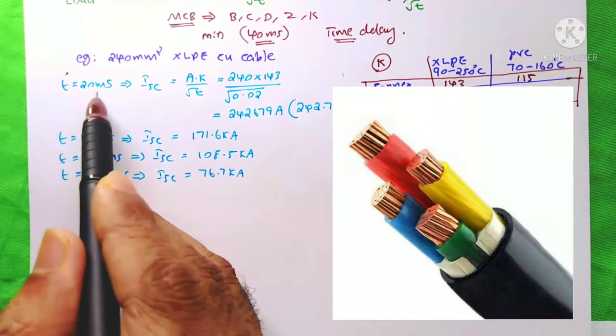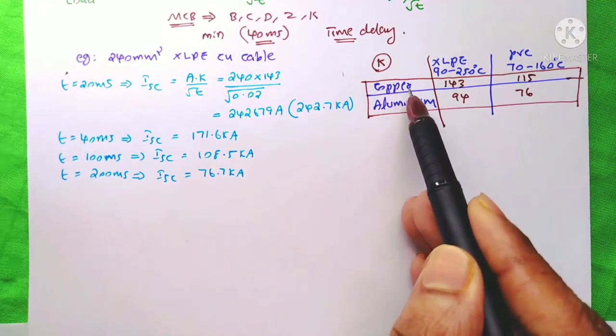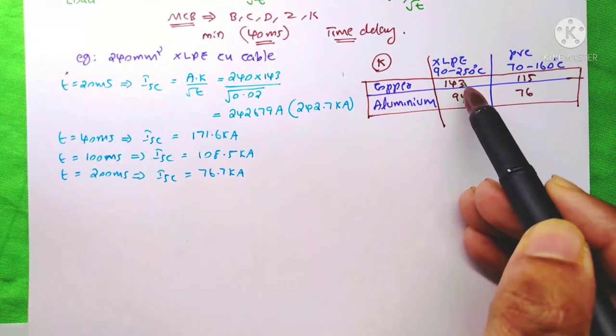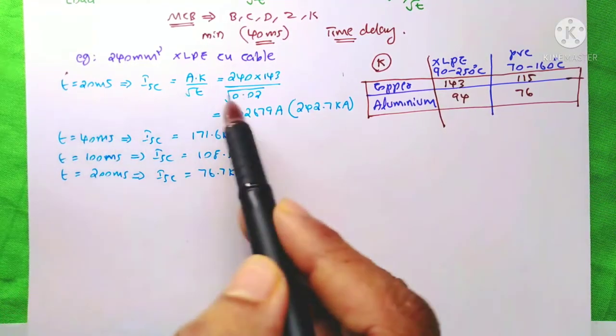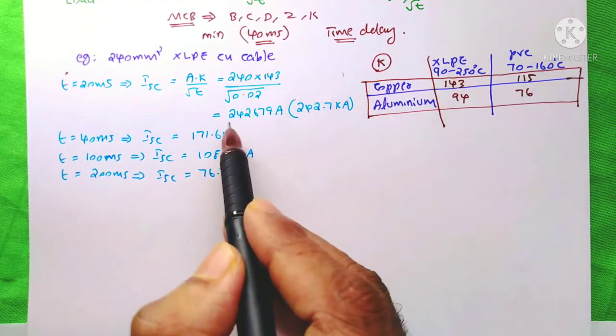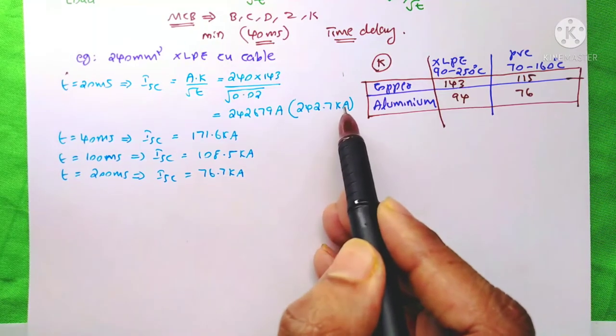When T equals 20 ms, for the constant K for copper cable, if XLPE insulated, K equals 143. 20 ms means 0.02, root of 0.02. So the answer is 242.7 kA.